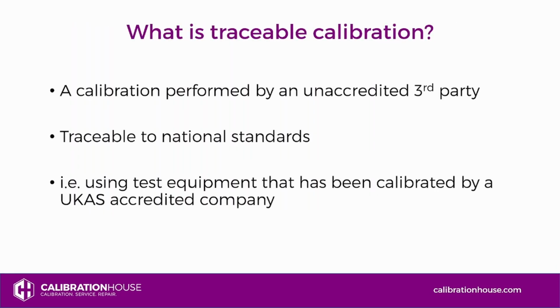So what is a traceable calibration then? This is a calibration performed by an unaccredited third party. They haven't been assessed technically, their staff have not been assessed, their processes have not been assessed. It is traceable to national standards because they can use test equipment that has been calibrated by a UKAS accredited company. For example, a weighing company would have their test weights UKAS calibrated, and then it is a traceable calibration, but their processes and their personnel have not been assessed and audited.